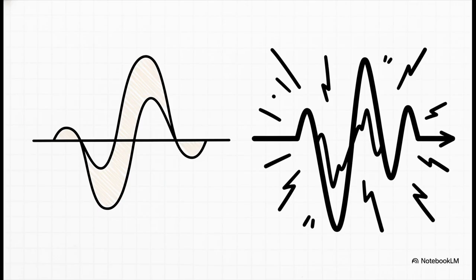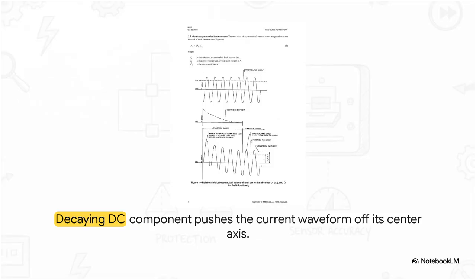Which brings us to a major complication: heavy fault currents and DC offset. What happens when the grid is under extreme stress? Well, during a power system transient, like a massive short circuit, the fault current is not some nice, clean, symmetrical wave. It gets messy, highly asymmetrical. Take a look at this decaying DC component. It literally pushes the entire current waveform off its center axis, creating a massive instantaneous fault current.